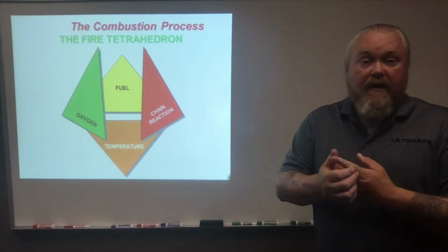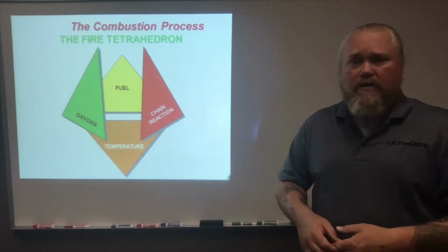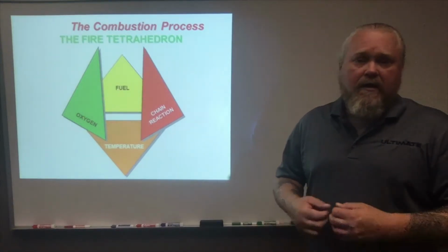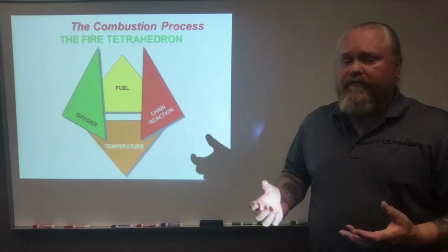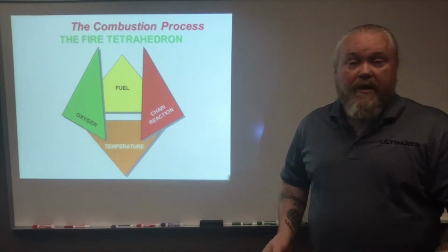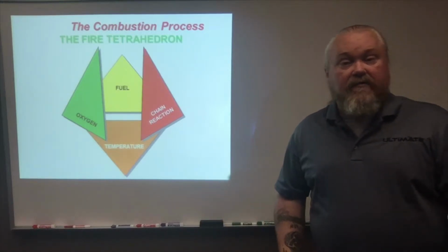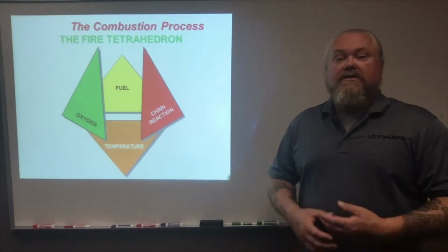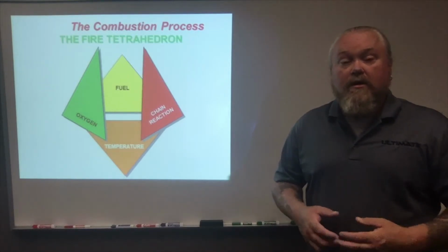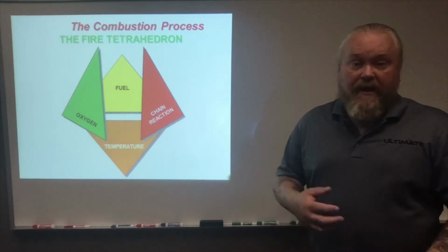There's also another factor that we can put into play, and that is the uninhibited chain reaction of those chemicals. That's where we get into systems, the older systems like halon, which actually don't take oxygen out of the air. They don't remove the heat, they don't remove the fuel, but flames cannot exist because of the chemical interruption. Now, since halon no longer has been manufactured in the world since 1994, we now have a new system called FM200, which pretty much does the same thing, but it's not harmful to the environment like halon is.